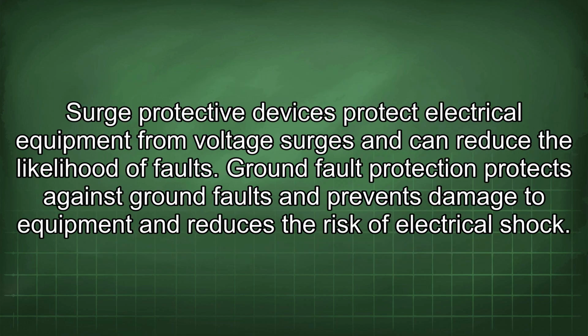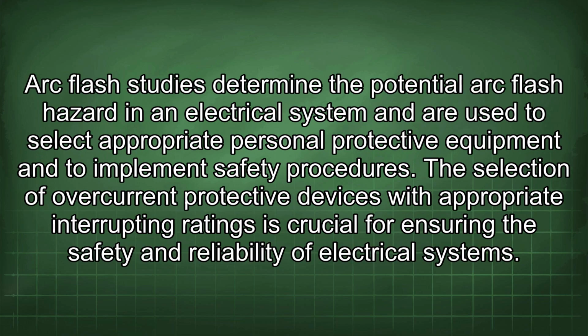Surge protective devices protect electrical equipment from voltage surges and can reduce the likelihood of faults. Ground fault protection protects against ground faults and prevents damage to equipment and reduces the risk of electrical shock. Arc flash studies determine the potential arc flash hazard in an electrical system and are used to select appropriate personal protective equipment and to implement safety procedures.